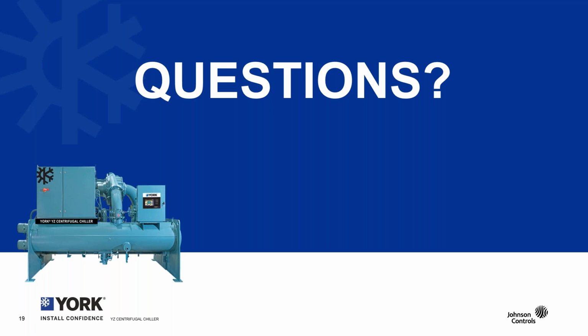It looks like there was a question, maybe it went kind of quick. Laura, can you go back to the efficiency of the product and just summarize that again, what the efficiency was at full load and part load? Absolutely. First of all, we use the phrase IPLV, the integrated part load value, a standard way of measuring how the chiller will perform in real world conditions, not just design conditions. For that, which is 90+% of the operating time for a chiller, we're talking about IPLV values as low as 0.297 kW per ton, and we've solidly broken the 0.50 kW per ton barrier for full load, with product readily available as low as 0.49 kW per ton. That's amazing.